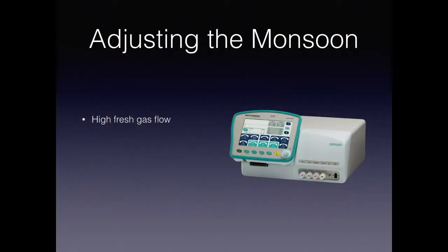But now they tell me that more than half of their sales are in the electrophysiology market. Okay, so what are the problems with this thing? First of all, it's putting out a lot of gas. You're typically putting out between 15 and 20 liters per minute of gas into the airway, so any CO2 that's there is getting diluted in that kind of flow.